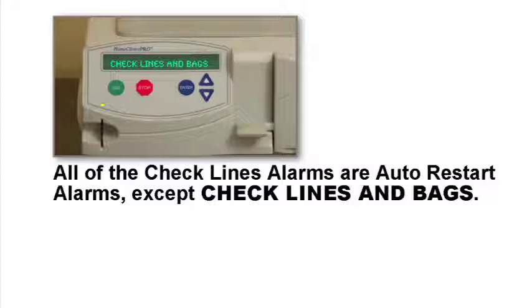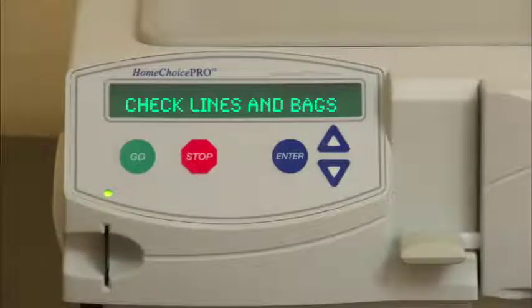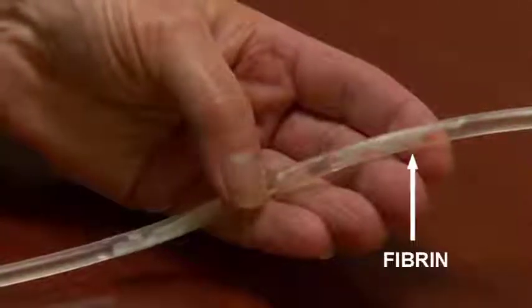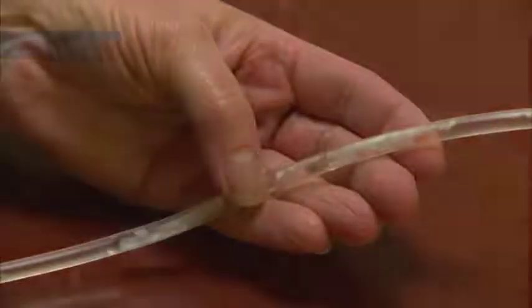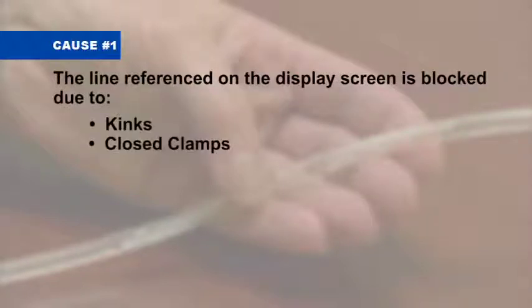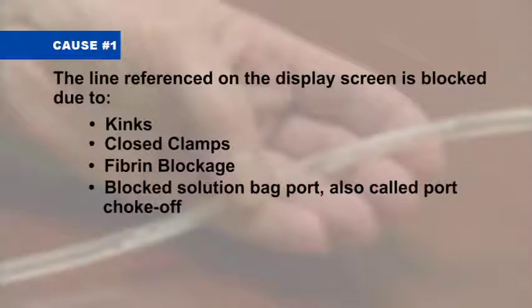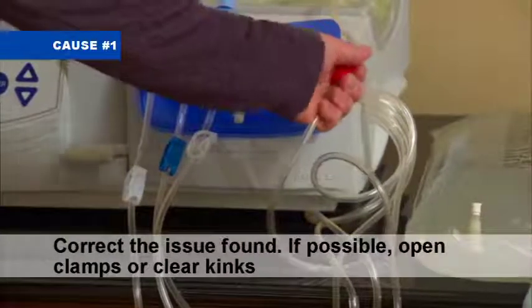All of the check lines alarms are auto restart alarms, except check lines and bags. The most commonly identified causes for a check lines alarm include: cause number 1. The line referenced on the display screen is blocked due to kinks, closed clamps, fibrin blockage, blocked solution bag port, also called port choke-off, empty solution bags. If cause number 1 occurs, correct the issue found.